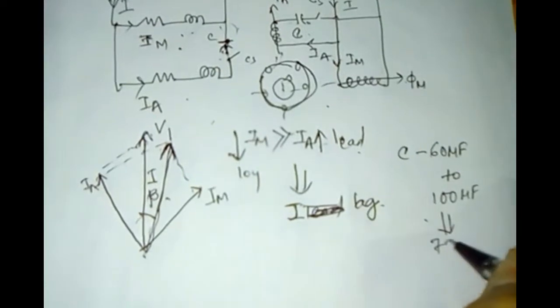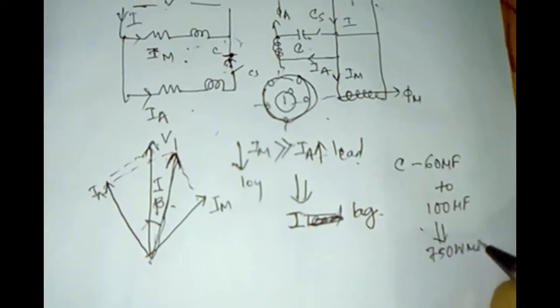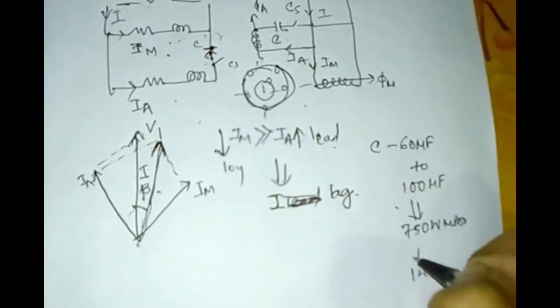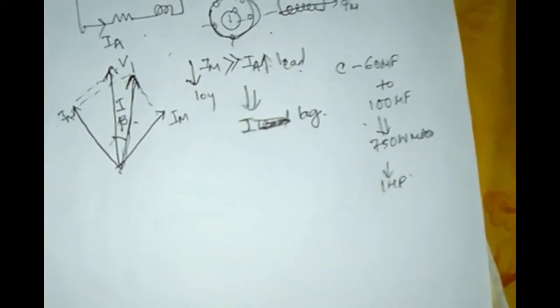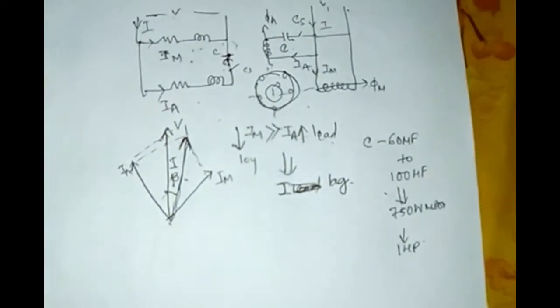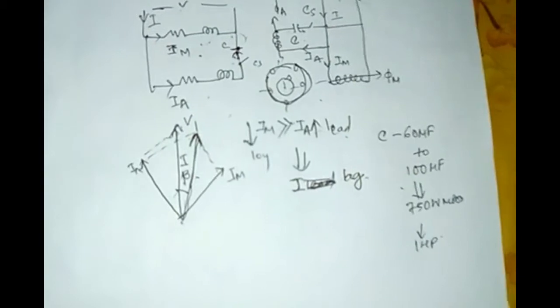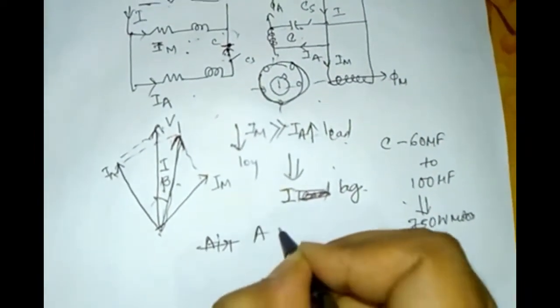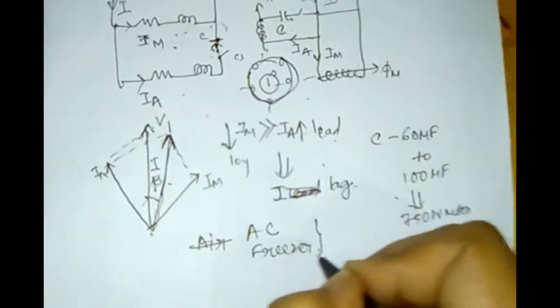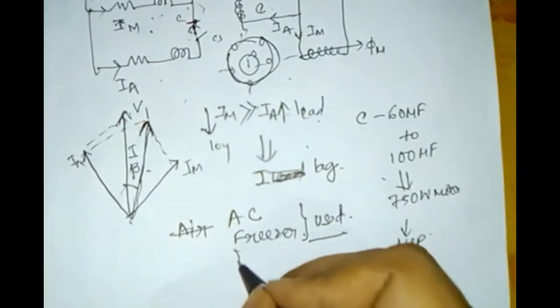The capacitor value varies from 60 microfarads to 100 microfarads for a 750-watt motor, which is equivalent to 1 HP. AC electrolytic capacitors are more economical and preferred, but the motor should not be started too frequently, otherwise the electrolytic capacitor may overheat or get damaged. Since the motor has high starting torque, it is used for refrigeration, air conditioning, freezers, and reciprocating pumps.